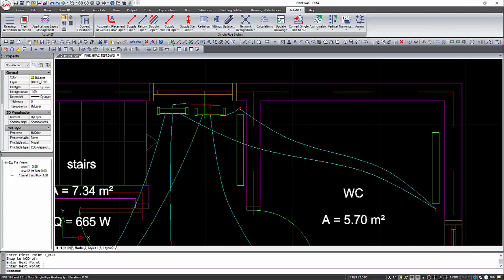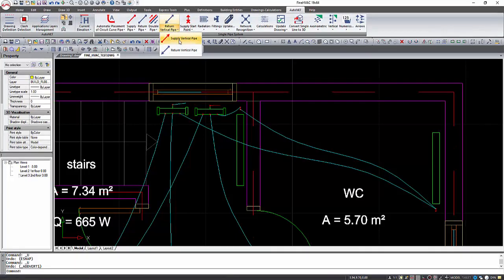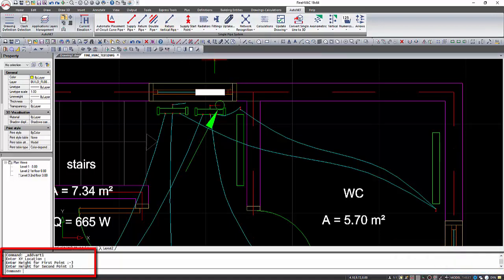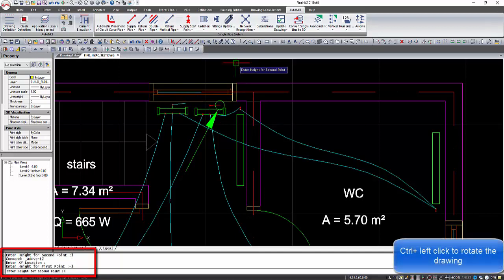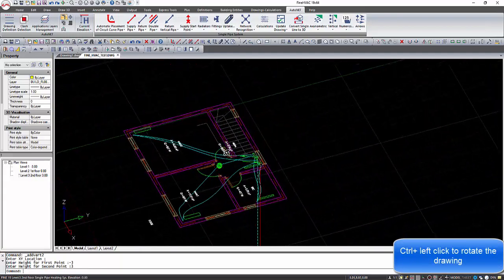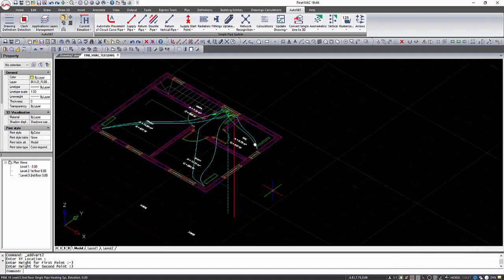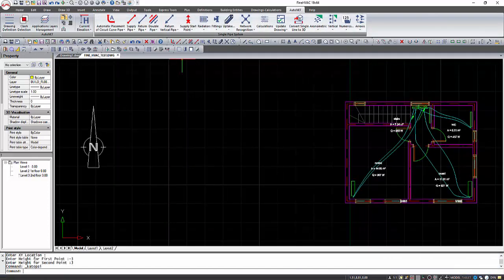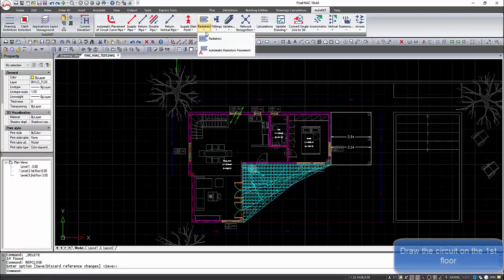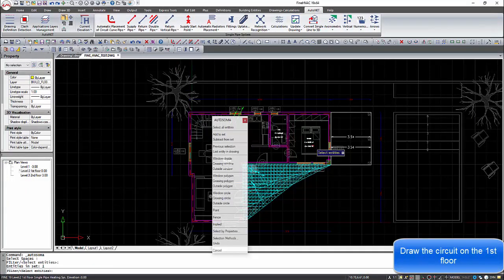After that, we need to connect the second floor with the other floors. When we want to draw a pipe that runs between the floors, we will use the vertical pipe command. First we define a point to place the pipe, then we set the height of the lower and highest point. In this example, the vertical pipe will connect the basement at minus three meters and the second floor at three meters height. With the same procedure, we can draw the circuit on the first floor.